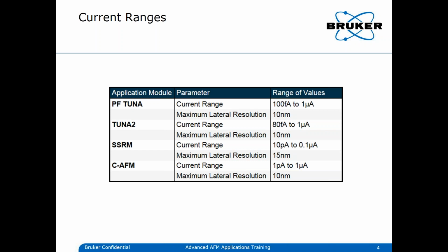The scanning spreading resistance microscopy is a different module capable of also measuring the current in the range from 10 picoamperes up to 0.1 microampere, so it's a much smaller range, but can be used for different purposes, like for semiconductors. The conductive AFM, which is let's say the oldest form of measuring tunneling current with an AFM, the CAFM, has a range from 1 picoampere to 1 microampere. Again, lateral resolution is limited by the tip and is about 10 nanometers.